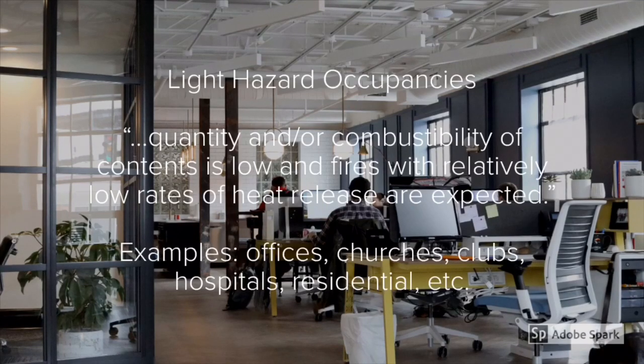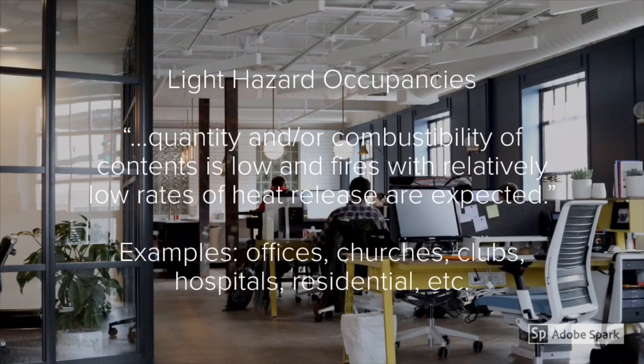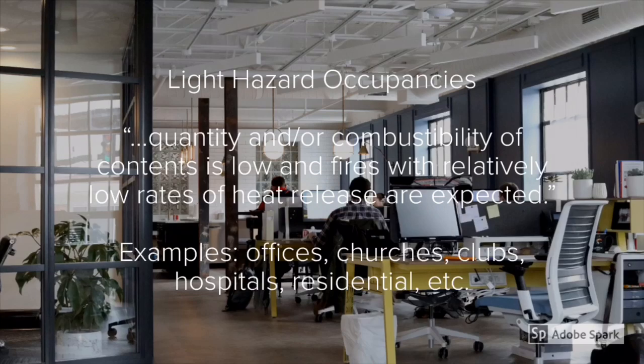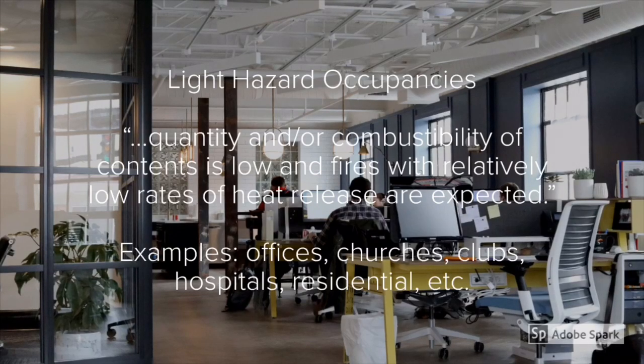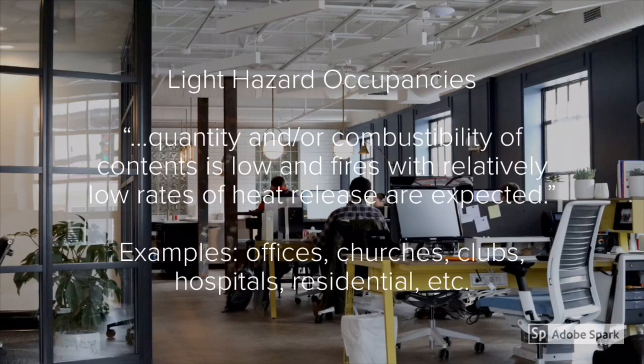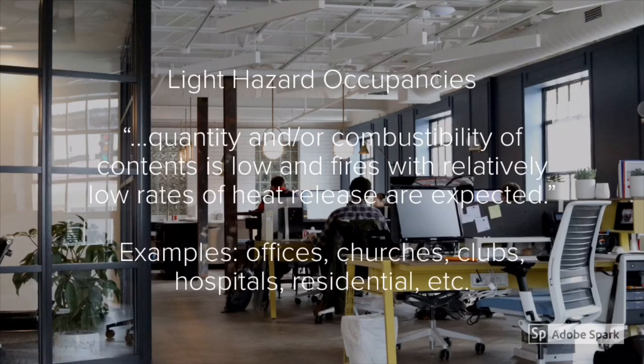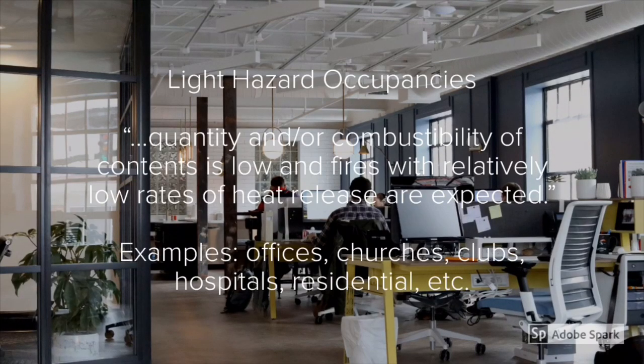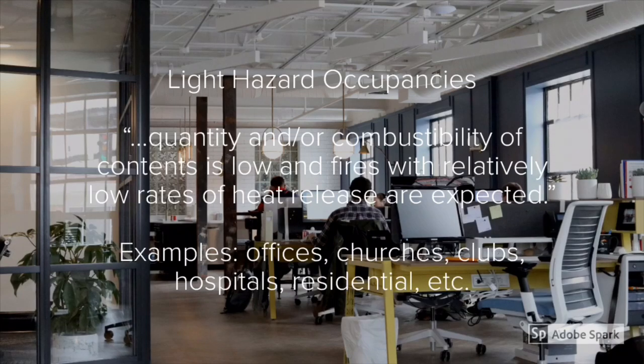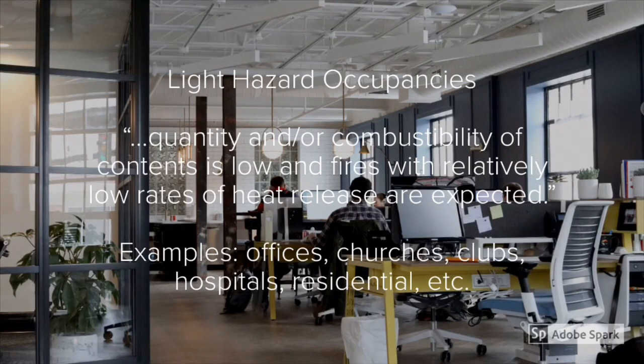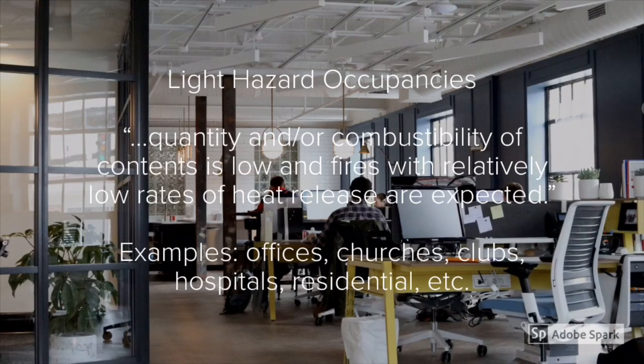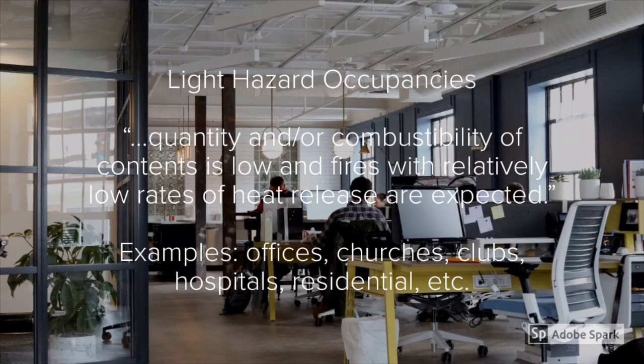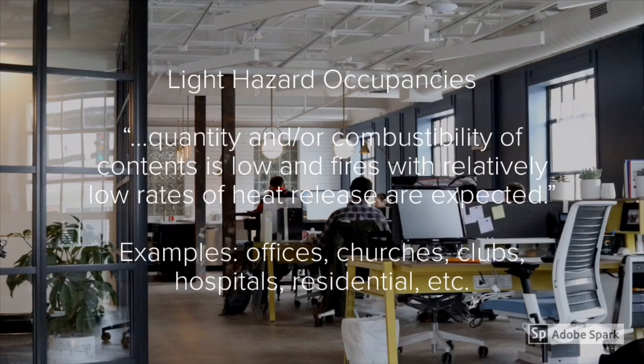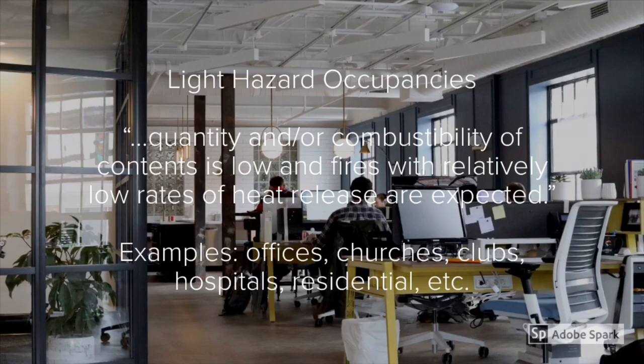NFPA 13 defines light hazard occupancies as those where the quantity and/or combustibility of contents is low and fires with relatively low rates of heat release are expected. Some examples of this are offices, churches, clubs, etc. As you can see, the picture in the background is of an office space. There's very little to burn, not a very high fire load. So our business occupancy would be a light hazard occupancy.